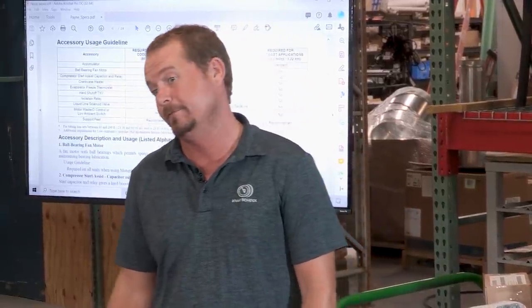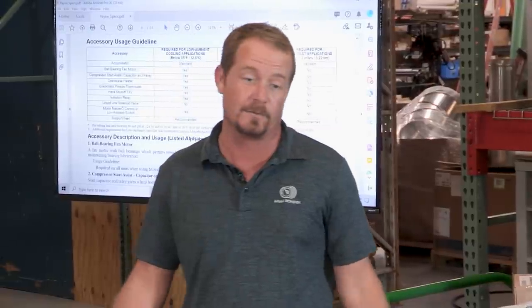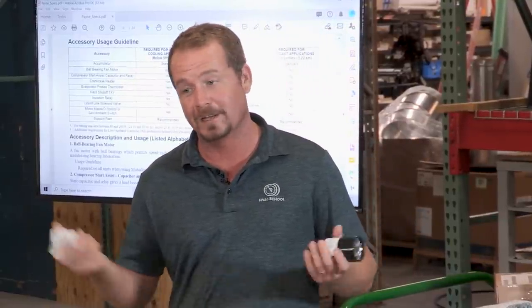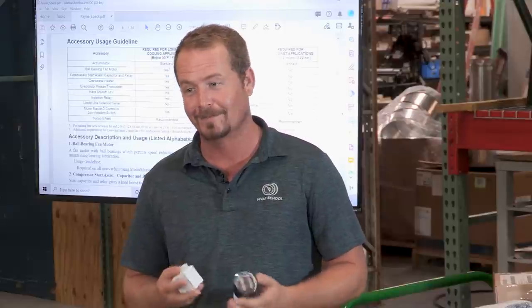Like, oh, hey, this started the compressor. That's great. You walk away. Three days later, it must have been going bad anyway because now it's failed. You know, if she was on her last legs, that's why she needed a hard start kit. It's actually a great line. You put it on because the lights were dimming. A week later, the compressor has a failed start winding. Well, you see, the lights were dimming because that compressor was on her last legs. She didn't have much life left in her, right?